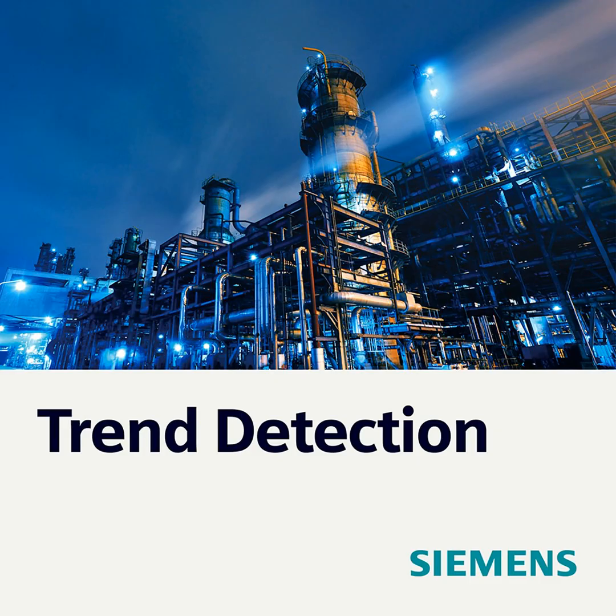How does a success case within the food industry look with Senseye? In the food and bev industry, we had a success case at a pump, for example. The bearings reached end of life, and I don't know if it's good to show in the webinar and the presentation, but Senseye detected, we had vibration data from this pump, and we detected a trend in the vibration in mid-January, and the customer worked on the asset or replaced the asset in mid-March.